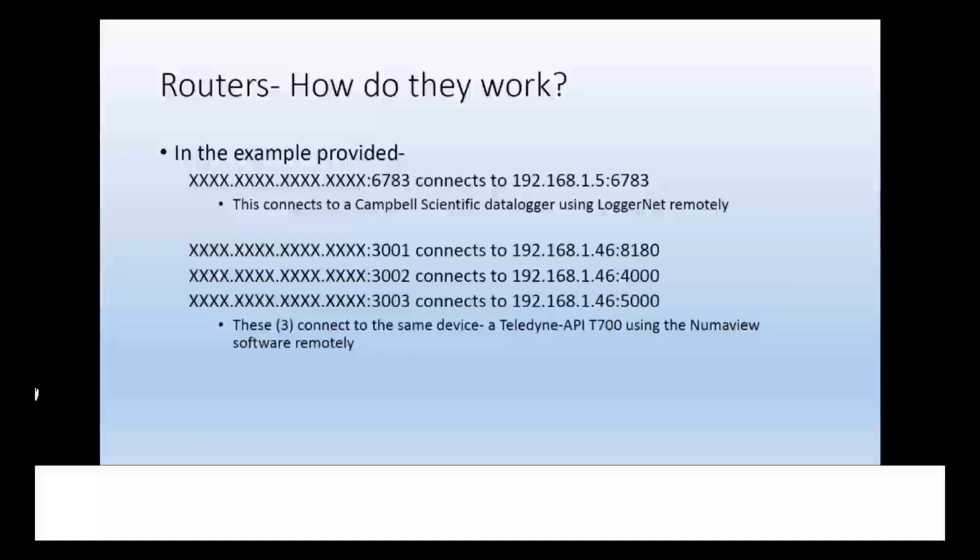The next example, where I use 3 different ports that are all connected to the same IP address, is actually using the NumaView software for the new Teledyne systems. So I can connect to Teledyne instruments remotely from my office. I can do Thermo instruments remotely from my office. That allows us to not only diagnose instruments, but also collect data directly from the instruments as well, because most of them have internal data loggers.